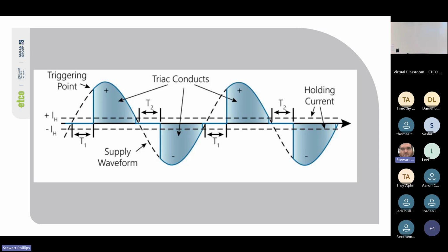So LED downlights, we can AC IR test by shorting out phase neutral to earth, but we cannot do that with our electronic dimmers, mostly because they are not actually connected to the neutral. So we need to be aware of that when we are doing our testing.